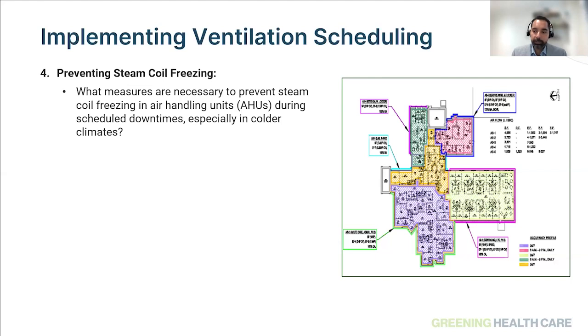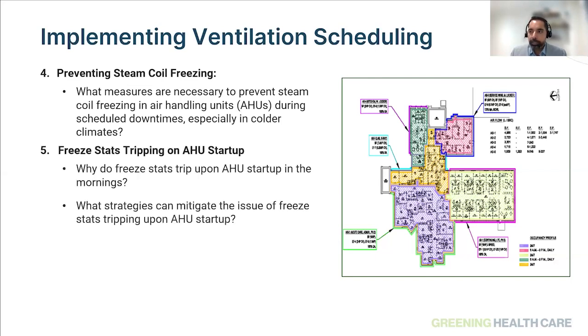Sometimes it's better to get half the savings if we can't get the full, rather than not applying anything to it. We touched on the freeze stat trips. Again, there are mitigations in ensuring that the freeze stat doesn't trip during the startups. And with the controls, it's practical to do all of these while you apply this with the scheduling. So the reason we brought these questions back to you is that these are some of the questions you're going to hear from your teams when you start to engage in scheduling those systems. They have been addressed in the past where hospitals have been applying these scheduling principles.